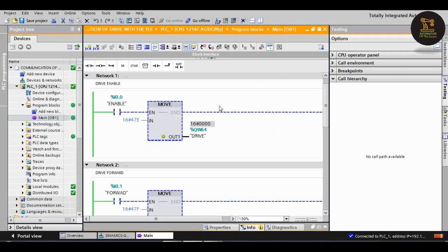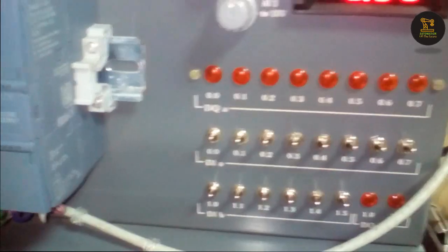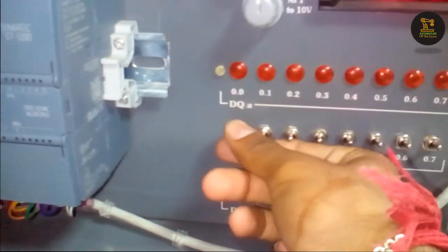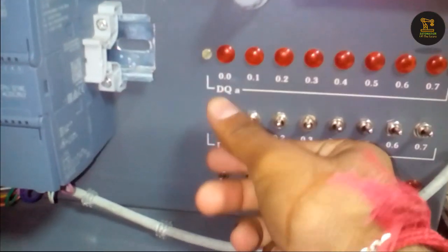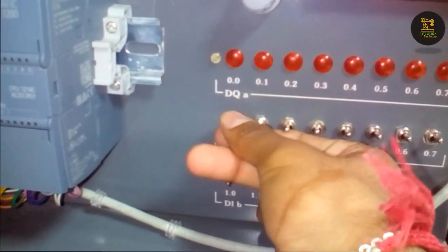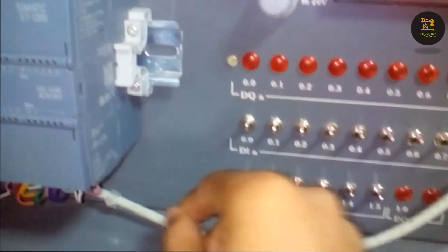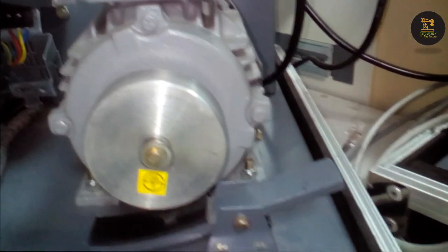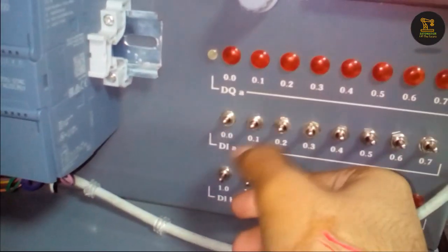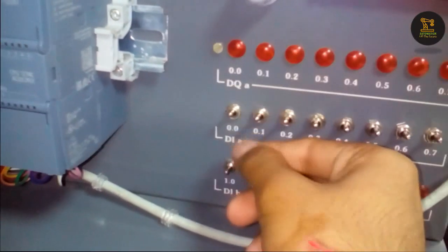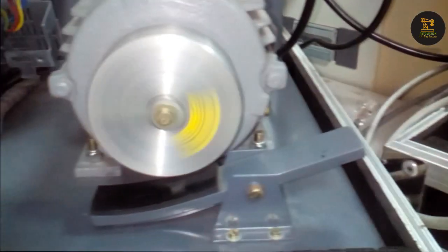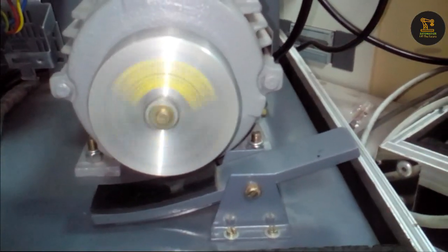Now let us check the drive. Now I enabled the drive. The drive is enabled now. And I am turning on I0.1, which is motor forward. The motor is rotating in the forward direction.